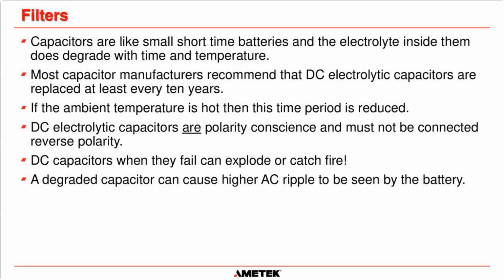DC electrolytic capacitors are polarity conscious and must never be connected with reverse polarity. That's how you let the magic smoke out. When they fail, they can explode or catch fire. A degraded DC capacitor can cause higher AC ripple to be seen by the battery.